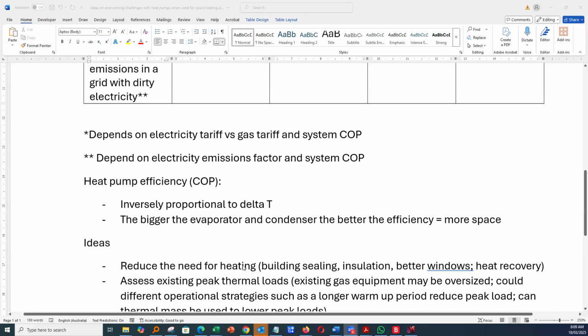The other things we can do is we can assess peak thermal loads. So the existing gas equipment could be oversized, and if it is oversized, we need to understand it. So we need to really assess those thermal loads, do some thermal metering, to understand the thermal loads on the system. And then once we understand those peak thermal loads, which is what the system needs to be sized for, we can look at strategies to reduce that.